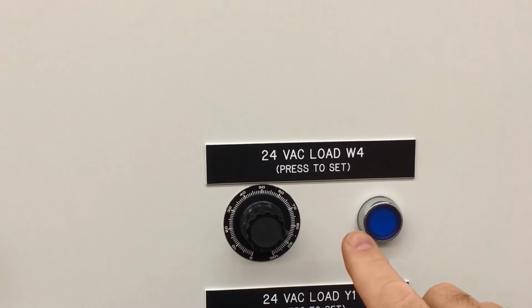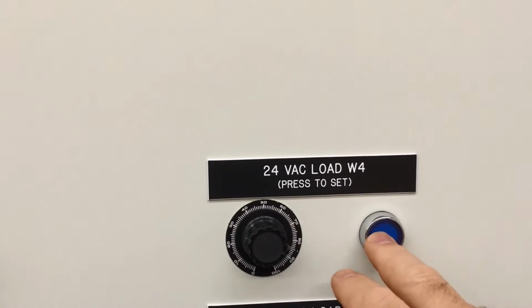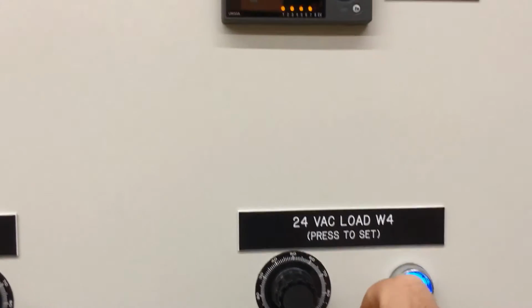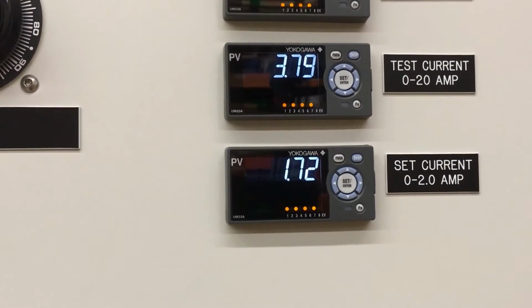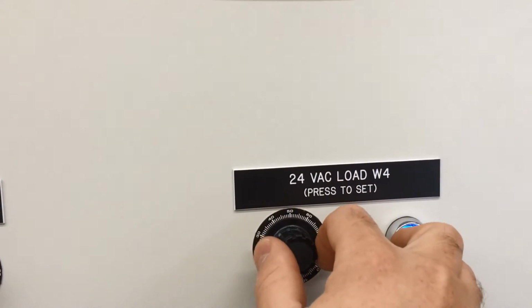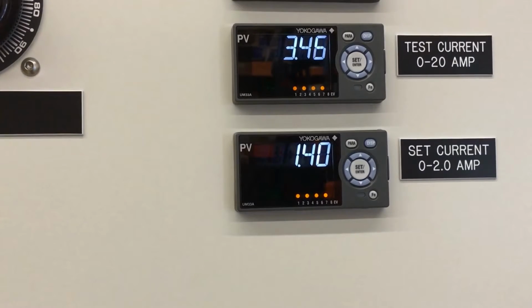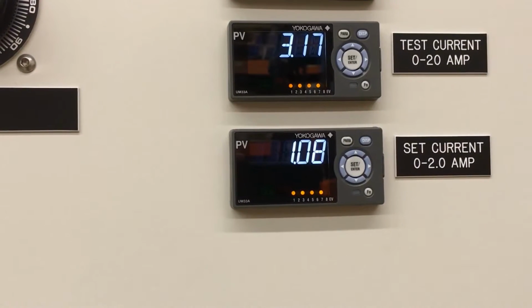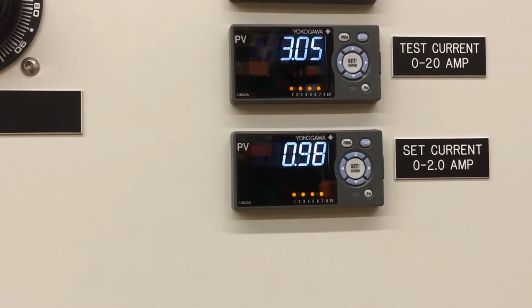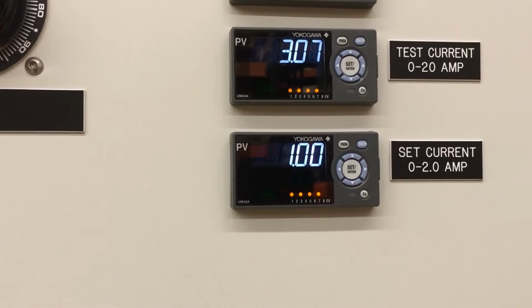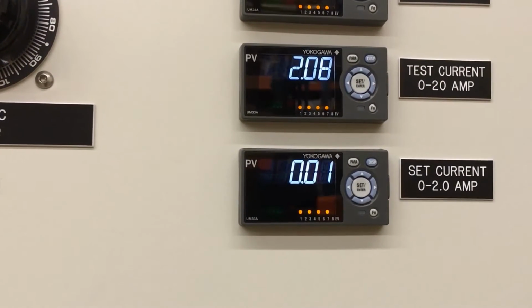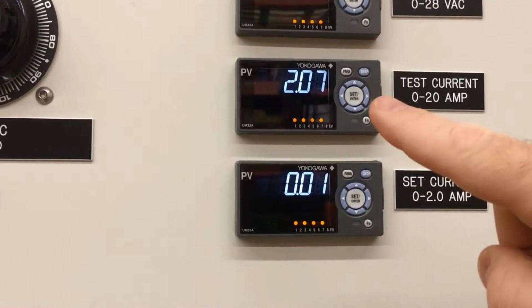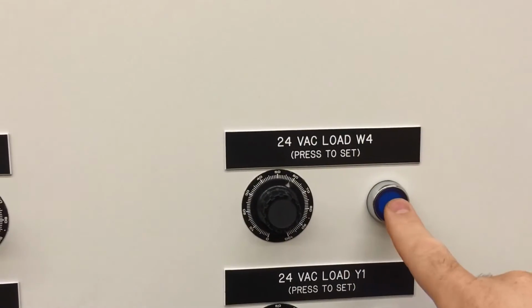So to set the current, press this button, and the load current reads out up top, for which you adjust it. And we'll adjust it down to 1 amp. And that's close enough. So now you can see we're back down to 2 amps because this load is turned off.